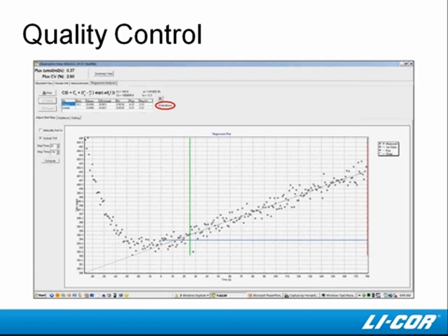In fact, here's an example where the data are noisy and the algorithm never converged to fit the exponential model. In this case, we reached 10 iterations without convergence, as you can see in the slide where iterations are circled in red. And the system only reported the linear flux values.